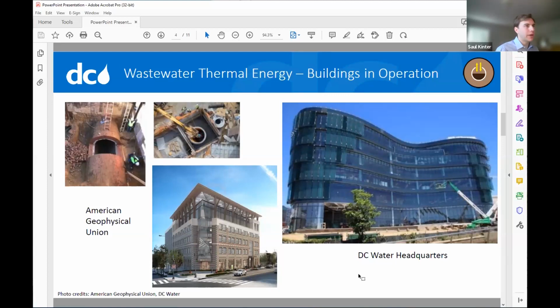We also have the DC Water headquarters, our primary office building, completed in 2018. We don't have any technical functions here; it houses our admin, procurement, HR, and customer service functions. It happens to be built on top of a sewage pump station, so we had very easy access to a very large amount of sewage flow. As part of the building's design, we required the designer to give us a proposal to incorporate wastewater thermal. Because of the relative ease of connection, it was by far the cheapest option for a high efficiency thermal energy supply.